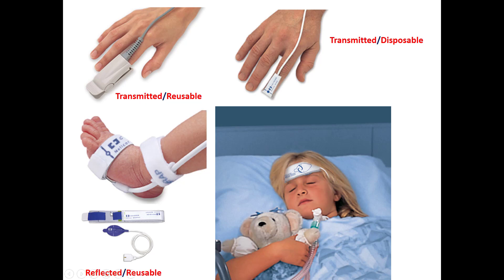Also transmitted and reflected types. In the transmitted type, the LEDs and the detector are facing each other, whereas in the reflected type, both the source and detectors are on the same side. This is an application for the reflected SpO2 sensor to measure blood oxygen saturation.